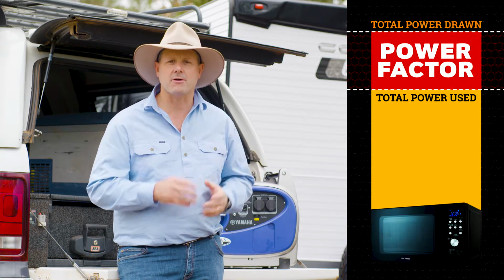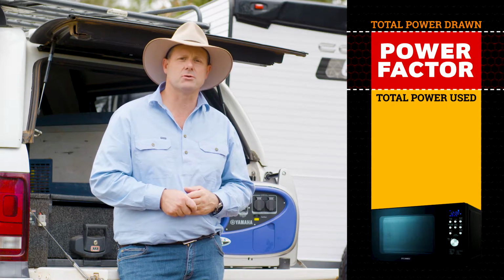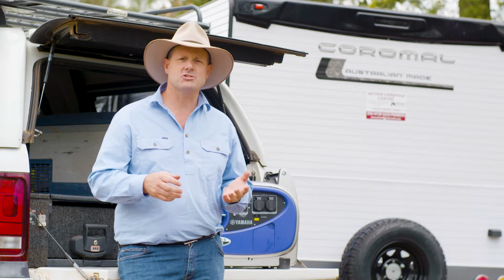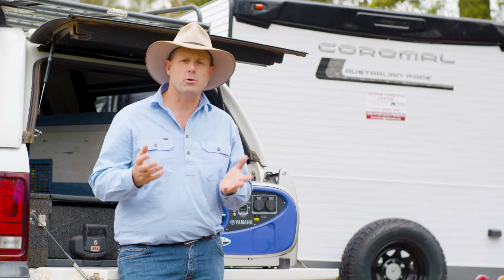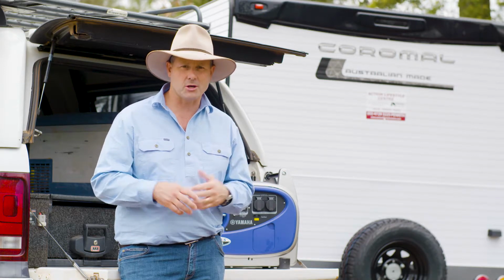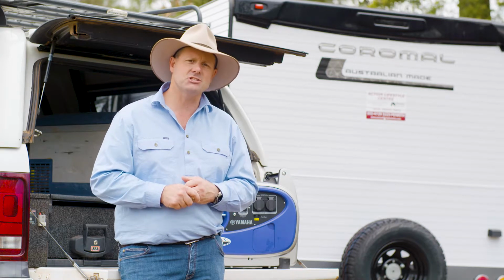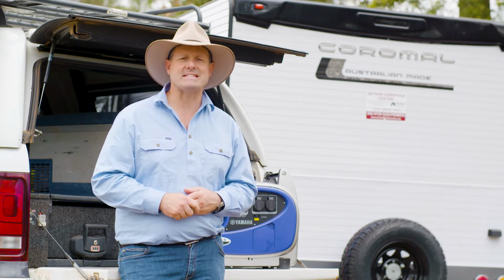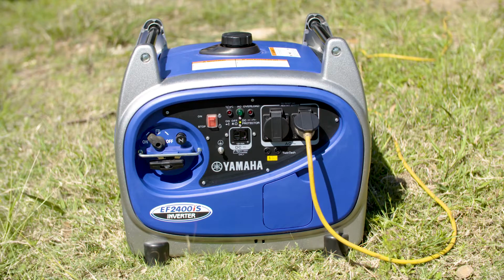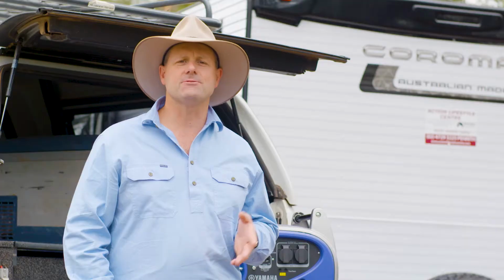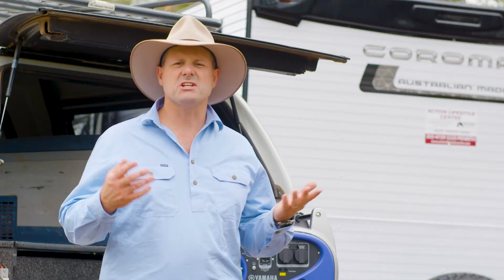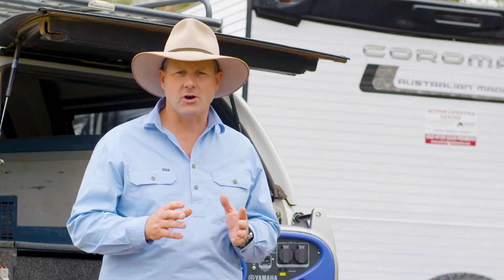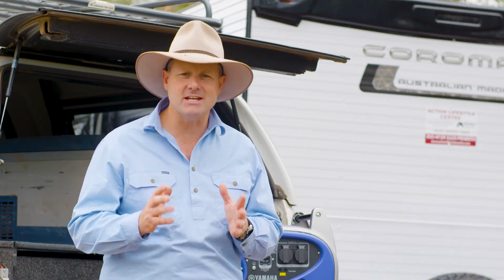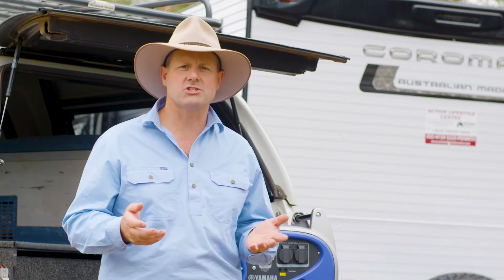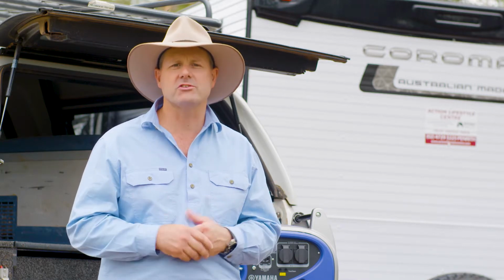Getting the exact power factor for each appliance is difficult, so as a rule of thumb, let's assume a power factor of 0.8 for all electrical loads. So in this case, a 2 kVA jenny spits out about 1600 watts. The catch is that a generator's quoted power is its peak rating, which it can only sustain for a short time. You have to dig out its continuous rating specification, which is usually about 80% of its peak rating.